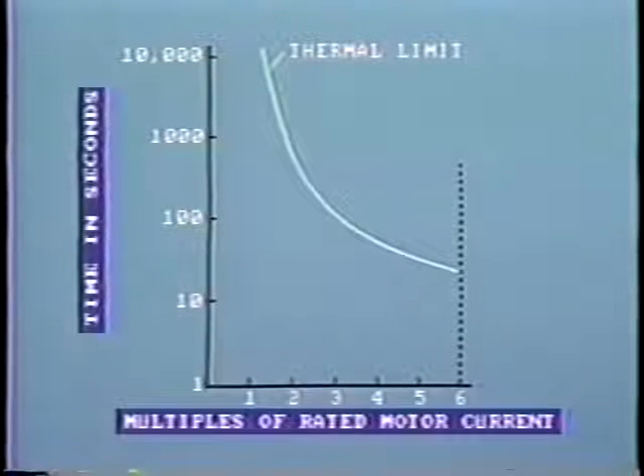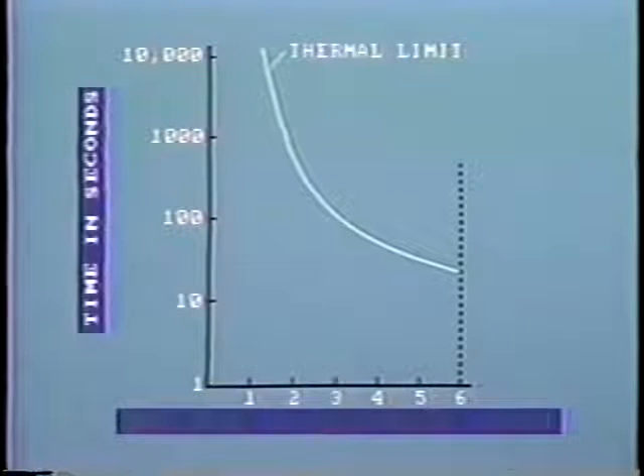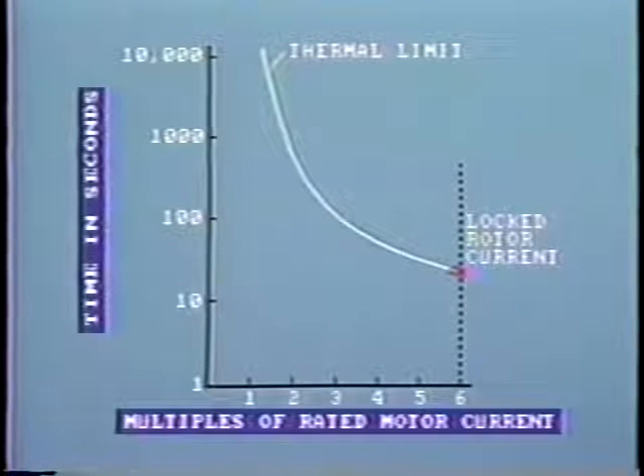For example, this curve provided by the manufacturer shows the allowable time for specific values of overcurrent for a particular motor. This shows that the motor is allowed to carry twice rated current for a period of 1,000 seconds, say 16 minutes. But it is only permitted to carry 6 times rated current for a period of 15 seconds. The thermal limit curve is actually a composite of several undesirable conditions. The upper portion shows limits of overload when the motor is in operation. The lower limit shows the locked rotor condition, that is, the magnitude of current and its allowable time limit.